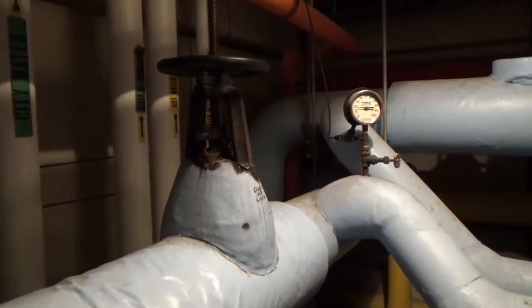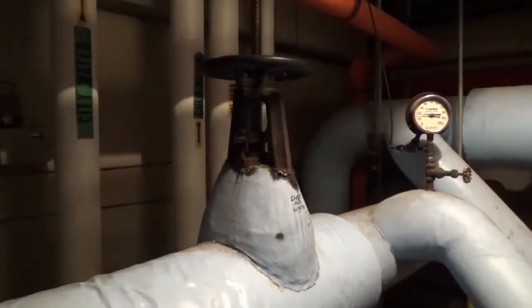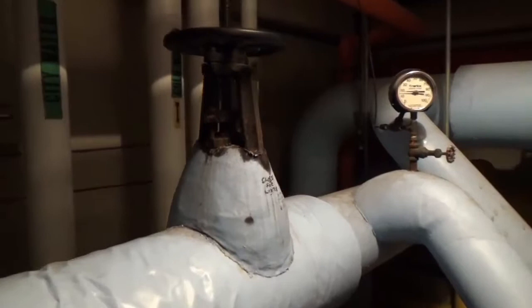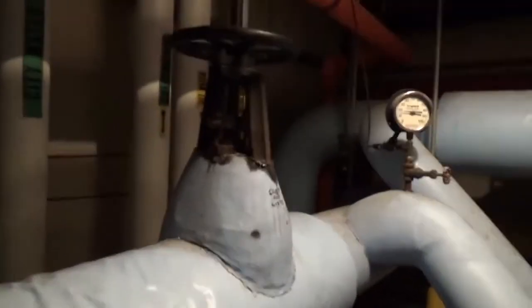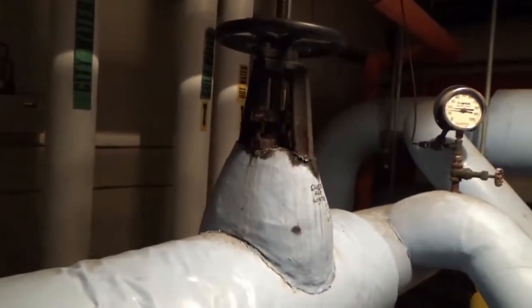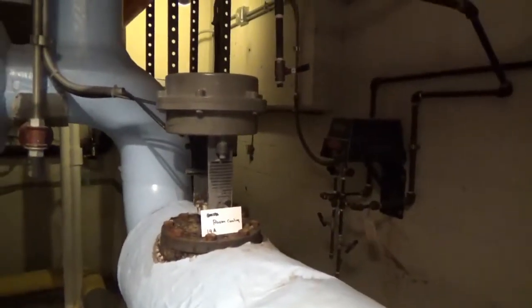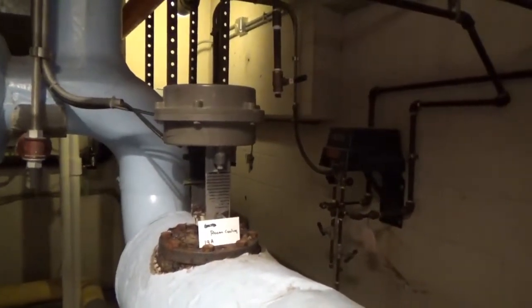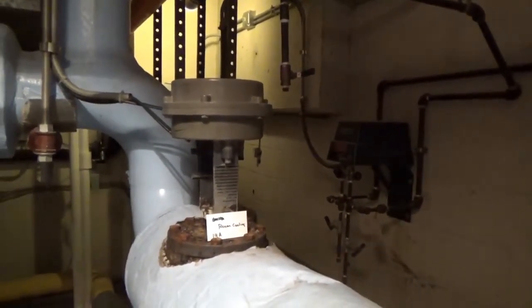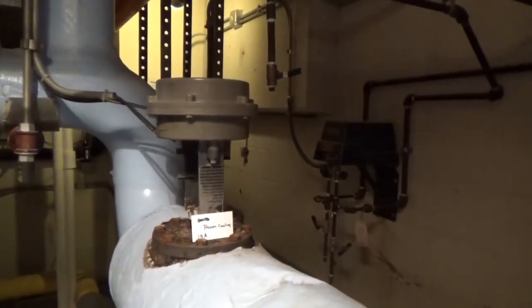This valve here is the valve that we use when we want to turn the air conditioning on in the building. So in order to turn the air conditioning on in the building, we'll come up here to 19A and we'll open this valve in the summertime. When that valve opens, water will flow down to this pneumatic actuator. This pneumatic actuator is what lets the water flow when there's a call for cooling. And we can control that down in the maintenance shop. We have an automation system down there. And then you just have to turn the pump on and you've got air conditioning.